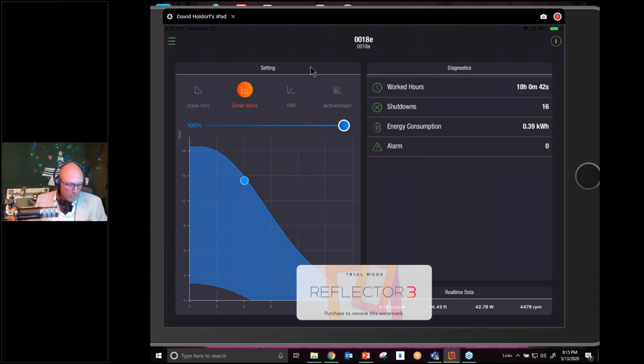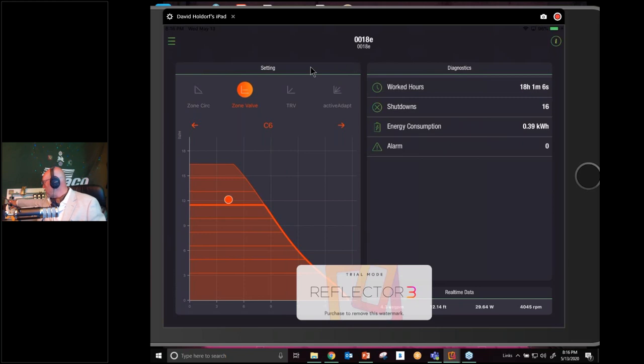Click on zone valve mode, and now you can see all the different curves available to you, and it's slowing down because the last time I was using the zone valve mode, I had set it for just about 6 foot of head. So that's the curve that it's lit up on. You can see that curve is nice and dark. You just tap the curve, and the circulator is going to speed up. You'll also see the light change on the circulator. I didn't touch the dial. We're in the Bluetooth setting on the dial, and now we're at just about 12 foot of head on the system. Or you can hit the arrows going back and forth to go up and down the different curves.